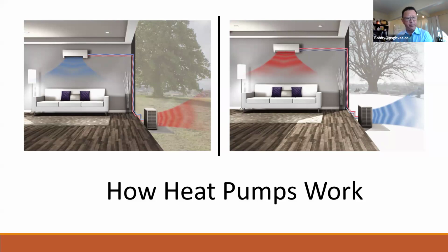So I do know that somebody in the chat mentioned the quick install of mini splits, and I'll just elaborate on that. If you see the red and blue refrigerant lines, we have a saturated liquid line and a gas line. Combined, depending on the insulation size, they are about the penetration of a tennis ball, if you can imagine that. So the hole from the inside to the outside is very small. And again, you have very small refrigerant lines going between the indoor and outdoor unit. And basically, that is how a heat pump works. Next slide.